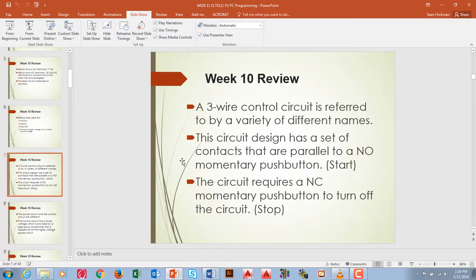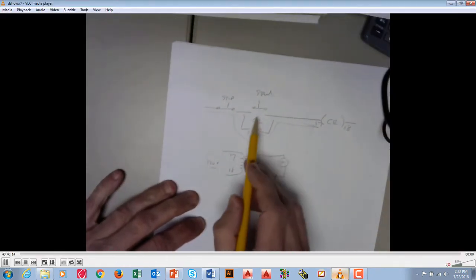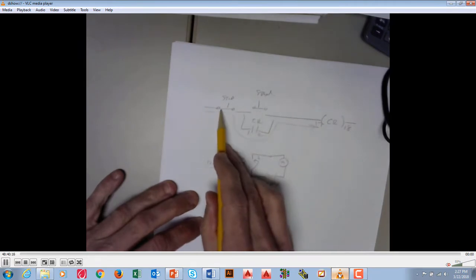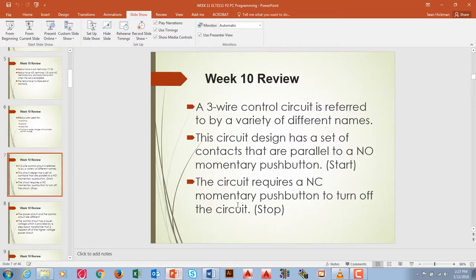Three-wire control is referred to by a lot of different names — seal-in, holding, memory, a latch. It had the normally open start and then normally closed stop. When we look at this, we see the normally open start and normally closed stop, because once it's energized, you've got to have some way to shut it off.